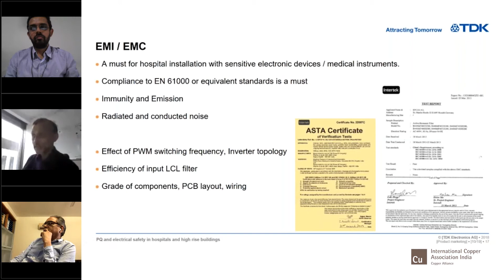Second, the noise must be at a higher frequency. A lot of people switch at low frequencies, 4, 5, 6 kilohertz. This graph shows where human beings can hear: from 20 hertz to 20 kilohertz, but the most sensitive range is around 4 to 5 kilohertz. If you create a problem at that frequency, the patient in the hospital will be very uncomfortable.